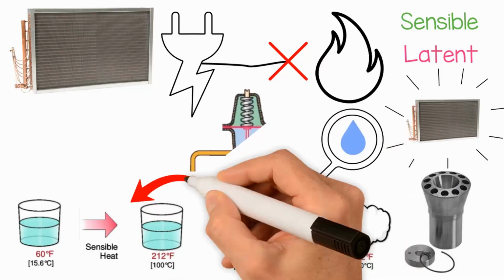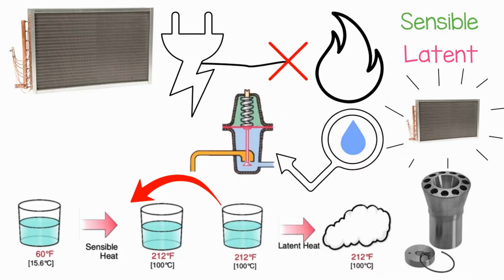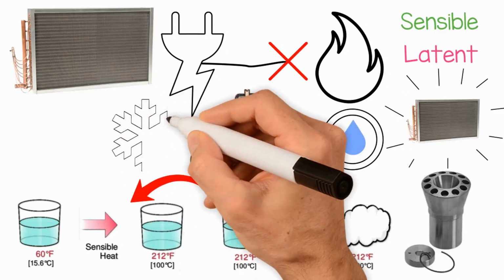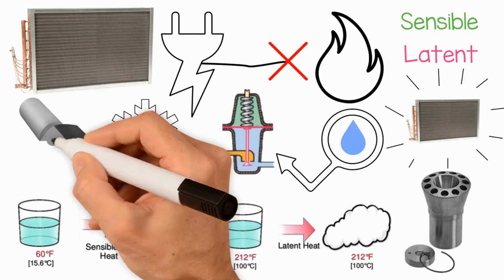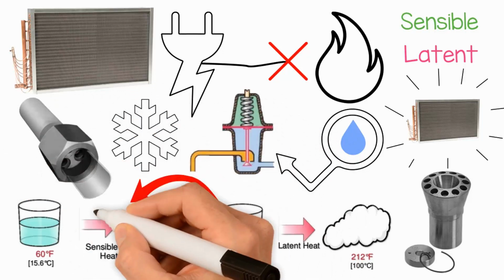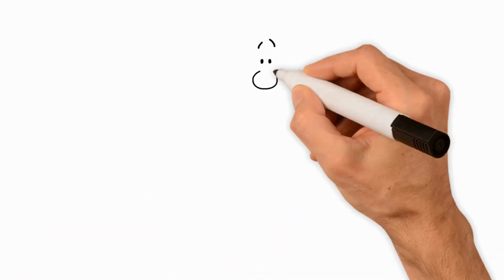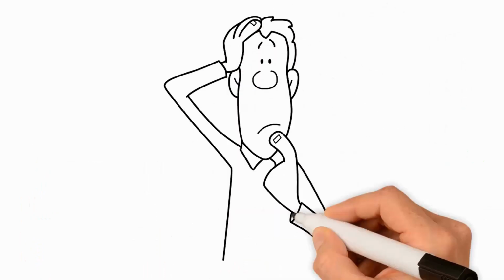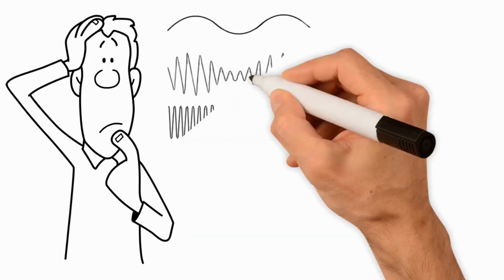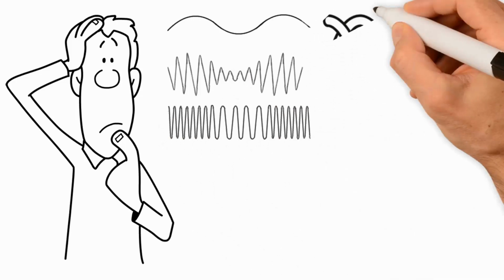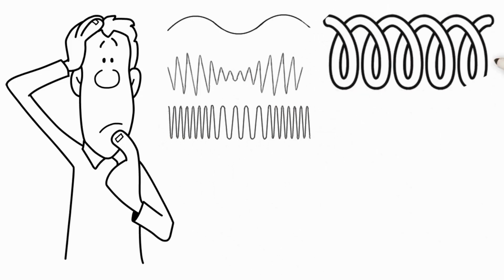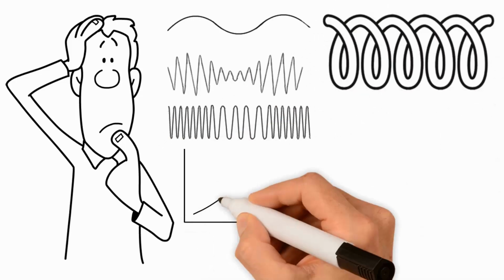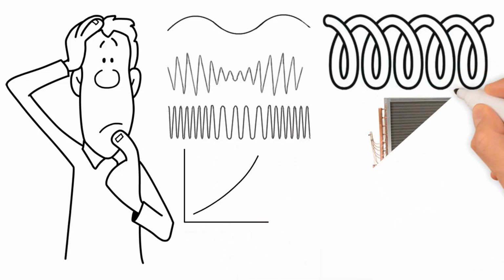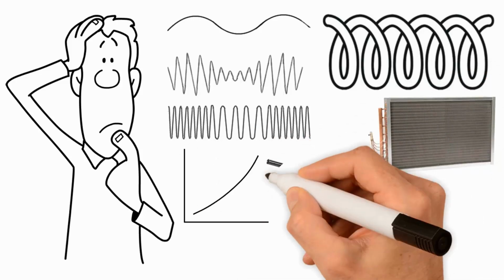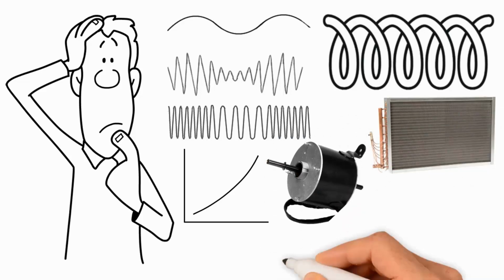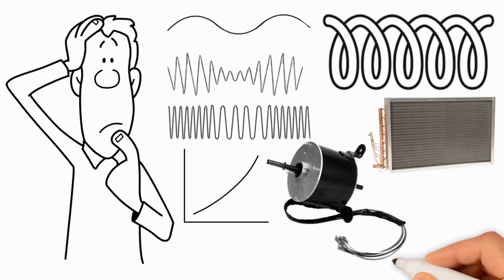We also developed an improved refrigerant metering device. Our refrigerant metering device is set up for natural refrigerants, so it's not a step controller, it's a constant flow controller. So what that means is that we're not based on steps, we're constantly modulating to get that superheat setting perfect, and the refrigerant running through the coil lovely, giving us a nice saturated condition in those new heat exchangers. Then we come to the motor. We work with the latest DC motors to reduce noise.